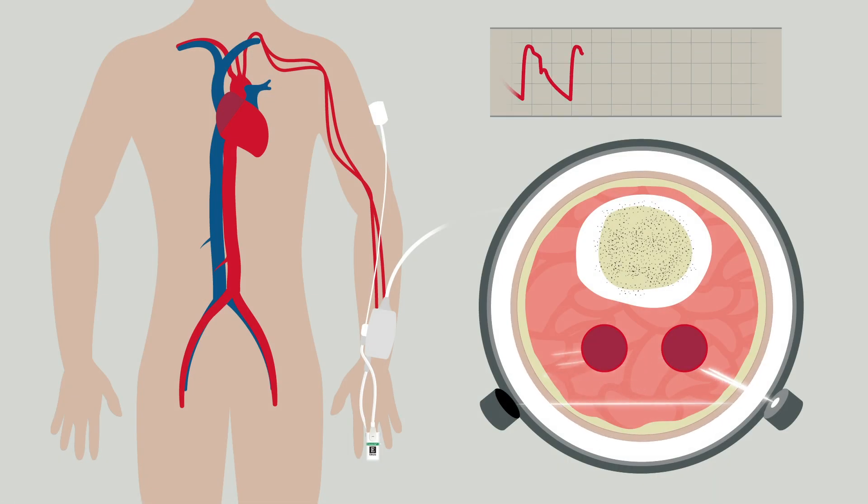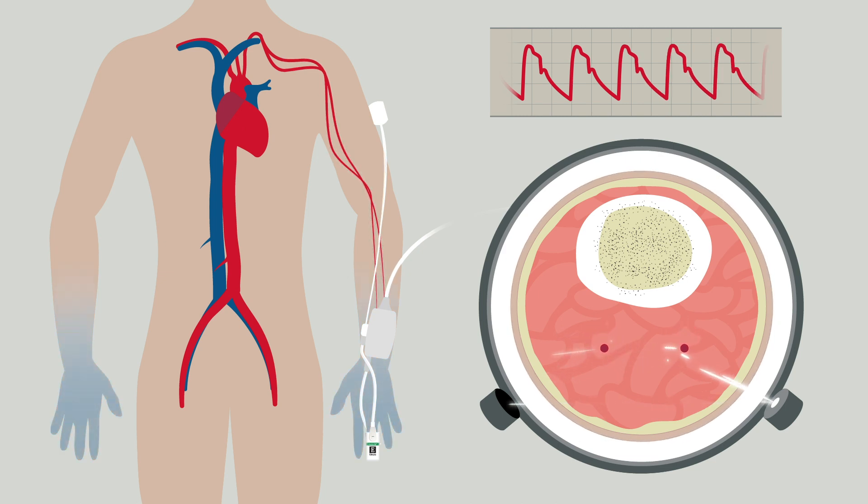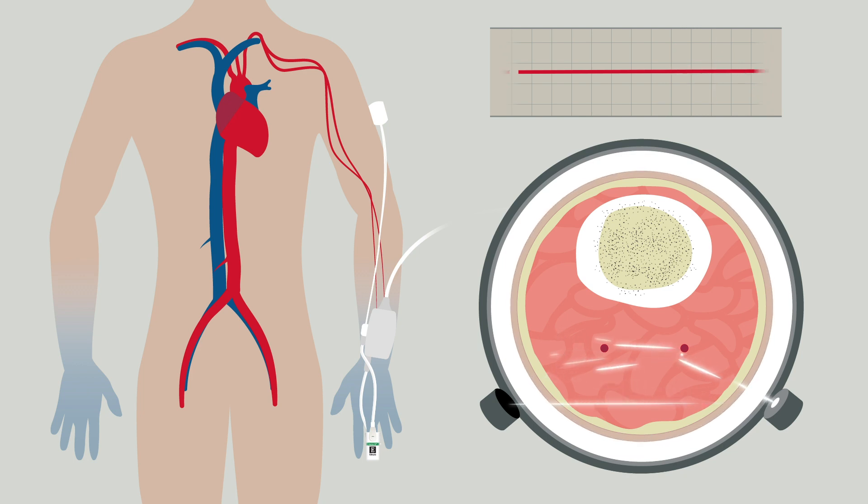One important physiological requirement for the non-invasive finger cuff is the presence of distal blood flow to the monitored finger. The stability and quality of the waveform and measurements are directly correlated to the presence of adequate distal blood flow. This is a key concept to remember when determining if a patient is appropriate for the non-invasive finger cuff or if an invasive arterial line is indicated.